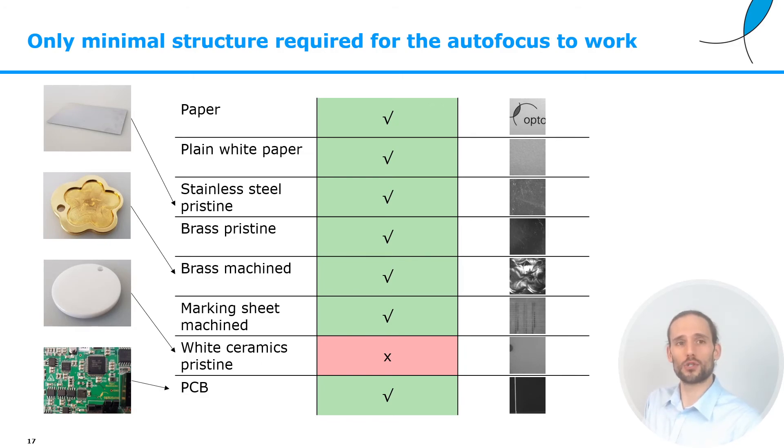As already mentioned before, this approach, the distance sensor, works very well for almost any material. And we found this out basically by seeing that autofocus requires only minimal structure to function properly. We have done tests on paper, stainless steel, brass, PCBs, and we've seen that for all these materials, the distance sensor works very well. The only problems we had were with white ceramics, and this is probably due to a lack of contrast, a lack of structure.